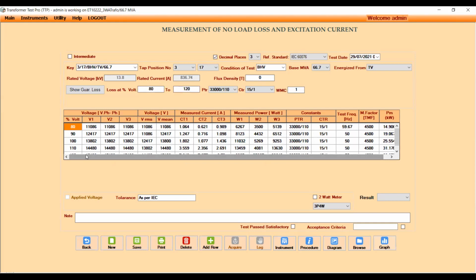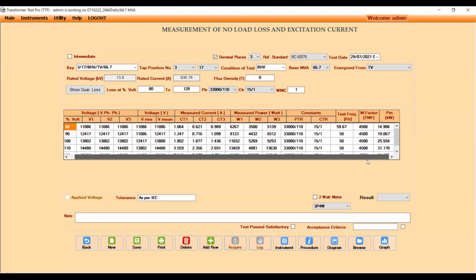In case of a bigger setup, you raise the voltage from the test bench with the voltage rise button. As soon as you see the voltage has risen to the rated voltage, you click on the acquire button at the bottom, and then all the values for the various voltages, the phase voltages, the VRMS, the V mean, the measured currents, the measured power, and the ratios for the PT and CT, the test frequency, the multiplying factor, and the measured power.